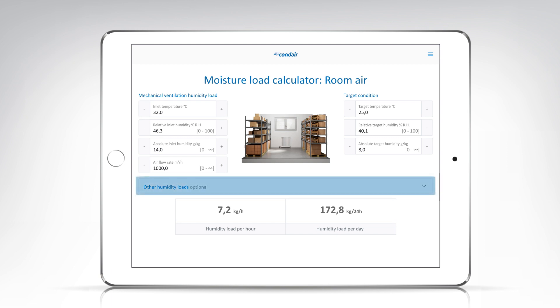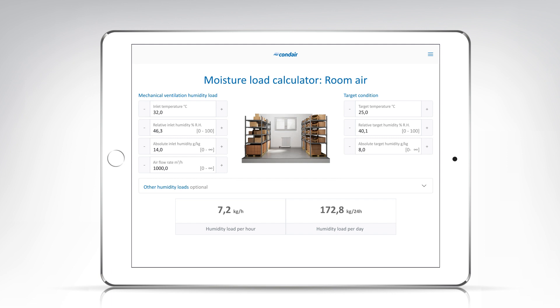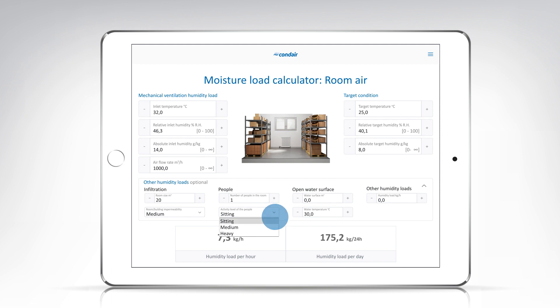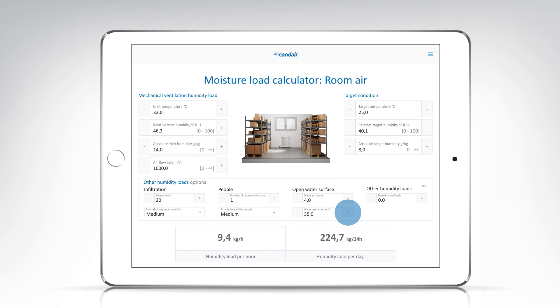In the center, there is an optional input bar in case there are other humidity loads in the room that you want to take into account in the calculation. Here you can, for example, add information about infiltration, the imperviousness of the room, or the activity of employees, and include them in the calculation. You can also take open water surfaces into account if there is a water basin in the production or storage room to be calculated.